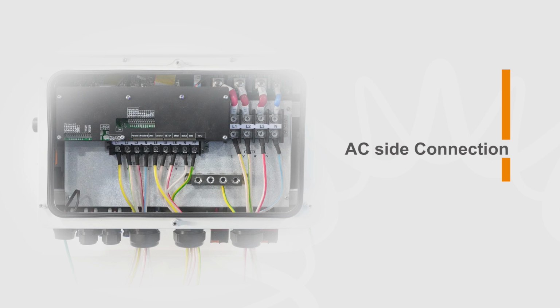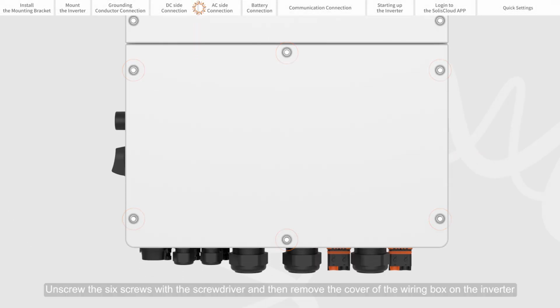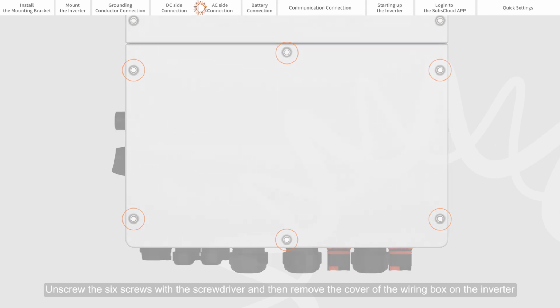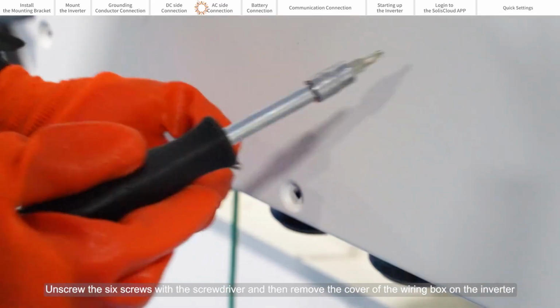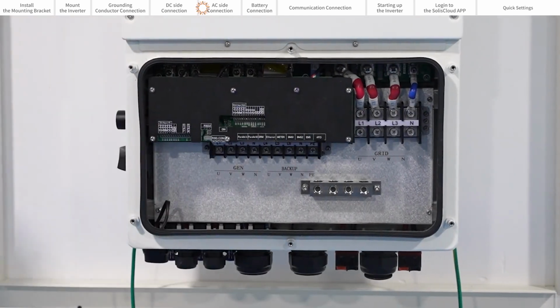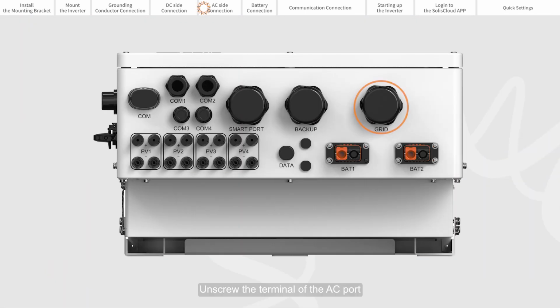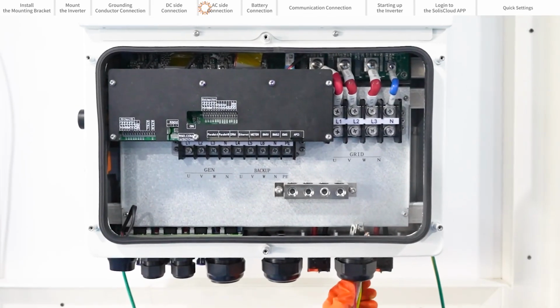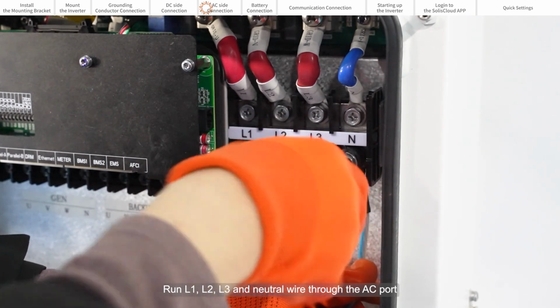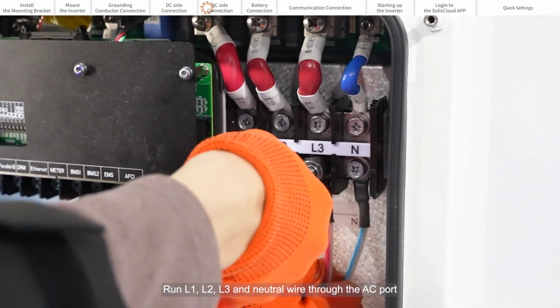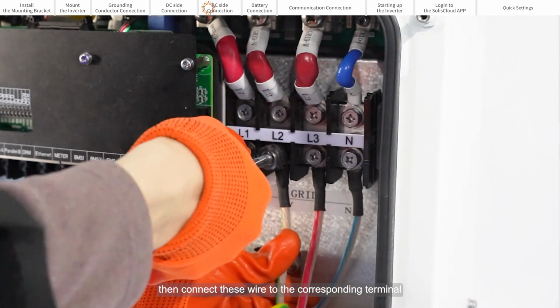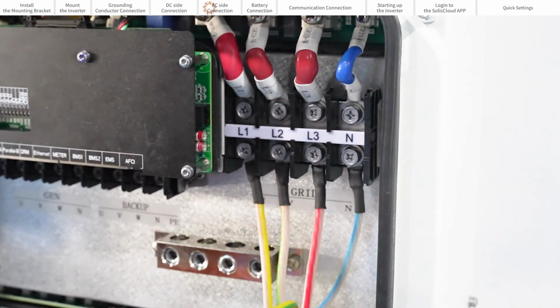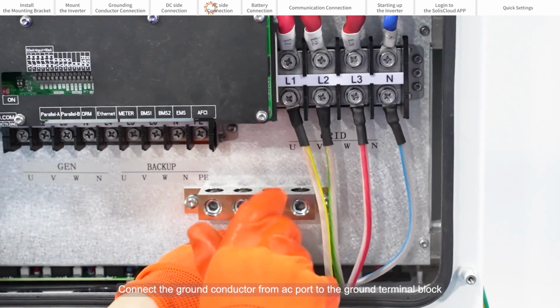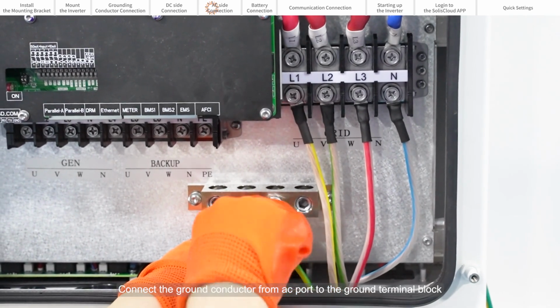AC side connection. Unscrew the 6 screws with the screwdriver and then remove the cover of the wiring box on the inverter. Unscrew the terminal of the AC port. Run L1, L2, L3 and neutral wire through the AC port. Then connect these wires to the corresponding terminal. Connect the ground conductor from AC port to the ground terminal block.